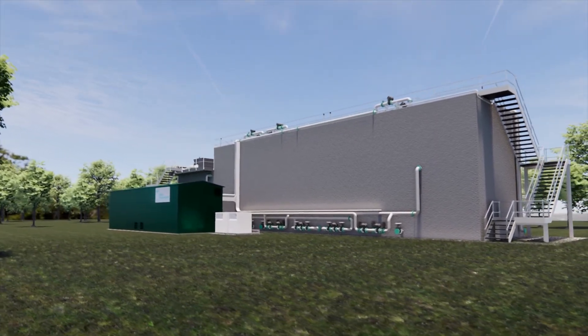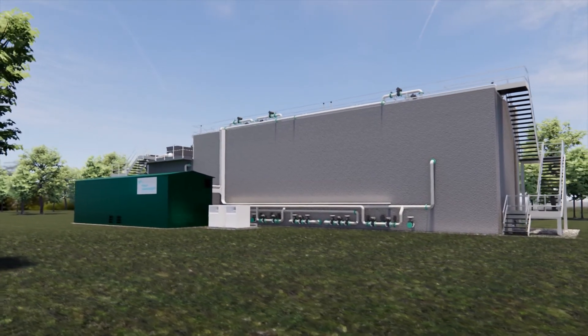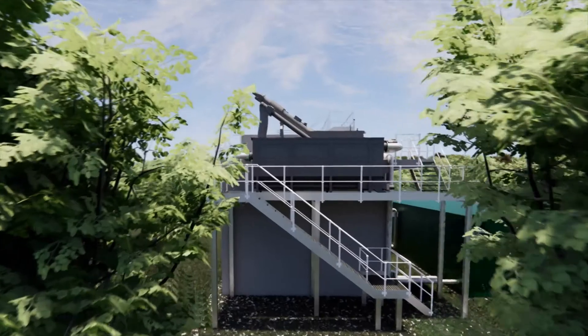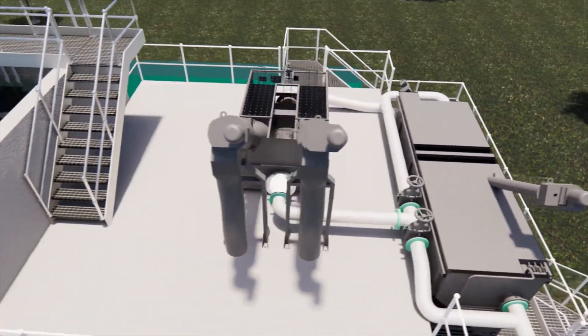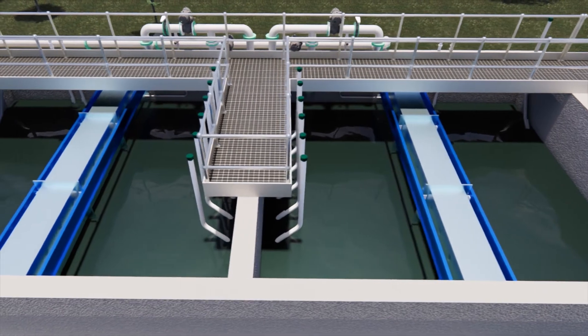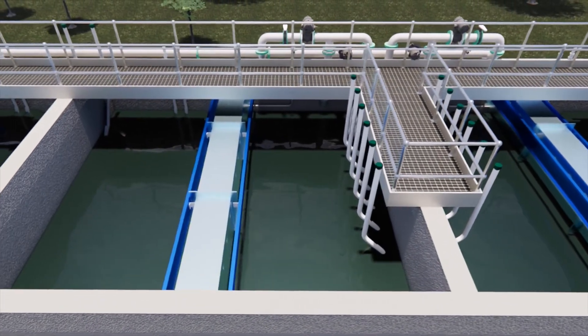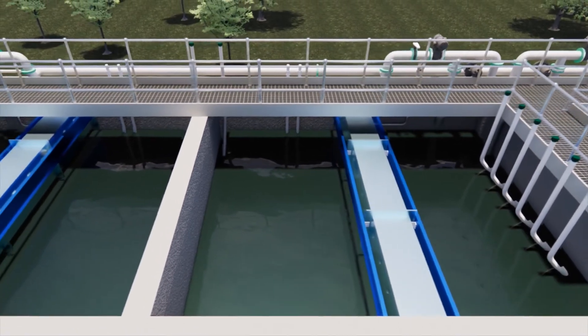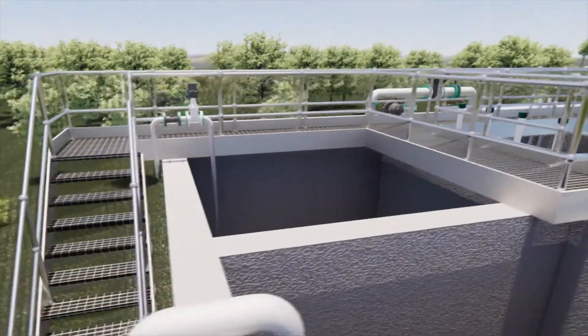We've taken the learning from the package plant and its benefits into what we refer to as the mini. The Nereda mini process is consistent with the package plant range. We have an influent buffer, typically two-thirds the volume of a reactor. Effluent enters the influent buffer through an inlet works, then fed through one of three reactors. After the reactor, effluent is sent to the receiving watercourse. Waste sludge goes into a sludge buffer, wasted to a treatment works for further processing, with supernatant returned to the influent buffer to be treated once again.